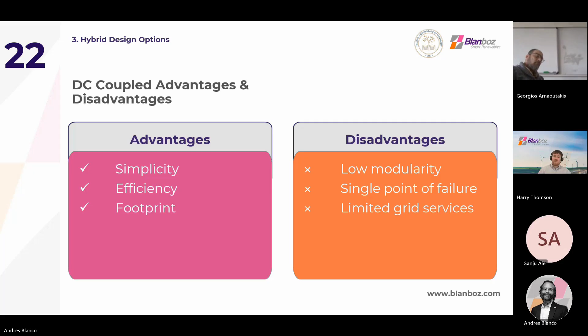Typically, it doesn't allow for stacking of multiple grid services, and this is because it is constrained by the single DC-AC converter, which often doesn't meet regulatory requirements. Now looking at the AC coupled system, the primary difference here is that the solar array and the DC battery have their own independent inverters before connecting to the transformer. This means that when charging the batteries from the PV or the solar array, the energy has to be converted from DC to AC and then back again from AC to DC to charge.